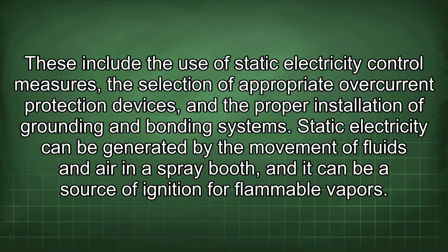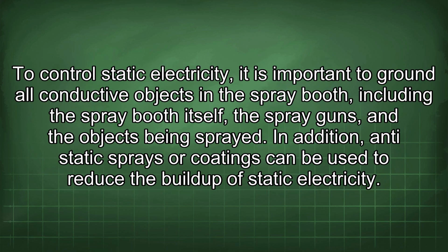Static electricity can be generated by the movement of fluids and air in a spray booth, and it can be a source of ignition for flammable vapors. To control static electricity, it is important to ground all conductive objects in the spray booth, including the spray booth itself, the spray guns, and the objects being sprayed. In addition, anti-static sprays or coatings can be used to reduce the buildup of static electricity.